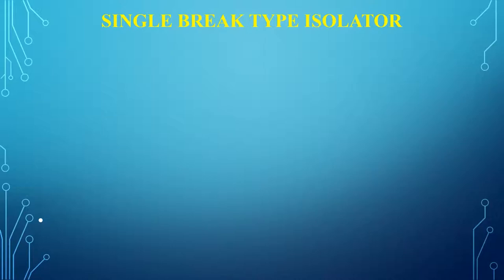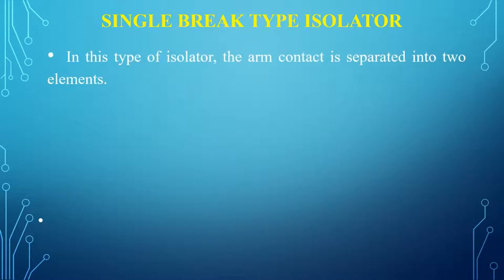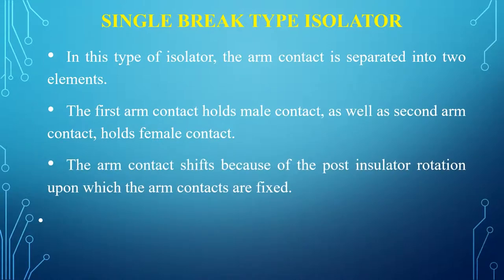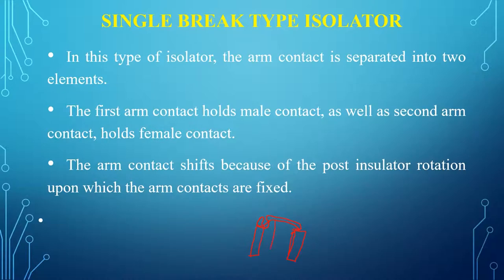The next type is the single break type isolator. In this type, the arm contact is separated into two elements. The first arm contact holds the male contact, and the second arm contact holds the female contact. The arm contact shifts because of post insulator rotation, upon which the arm contacts are fixed. The second element consists of a tubular rod that is fixed and operated with one more insulator.